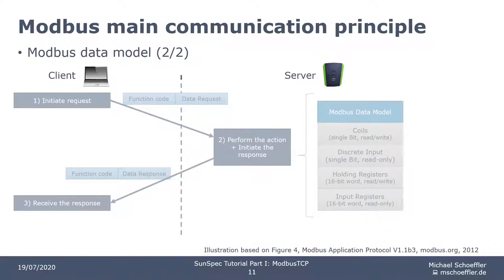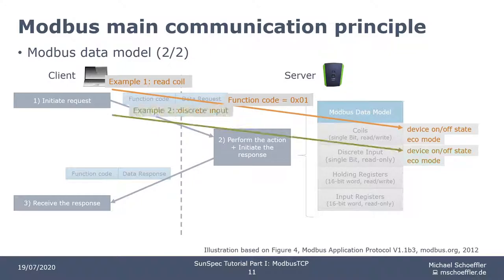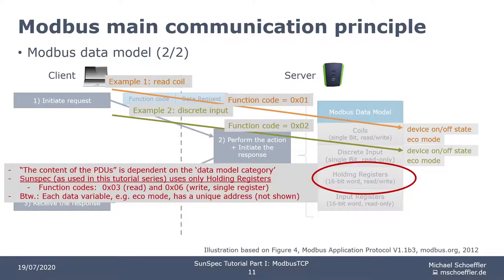Here's an example of how the choice of data model affects the communication. Let's assume device on-off state and ECO mode belong to the coils category and you want to read the data. Then you, as a client, send a PDU to the server. In this case, you have to set the function code to 1, because 1 is the function code for reading coils. Here's another example where the same data belongs to the discrete input category — in this case, the function code is 2. So the content of the PDUs depends also on the data model categorization. By the way, SunSpec uses only holding registers, which makes things a bit easier.